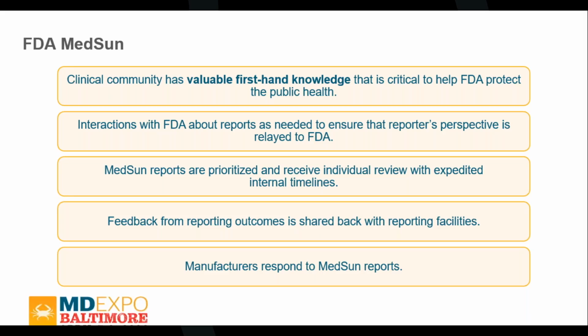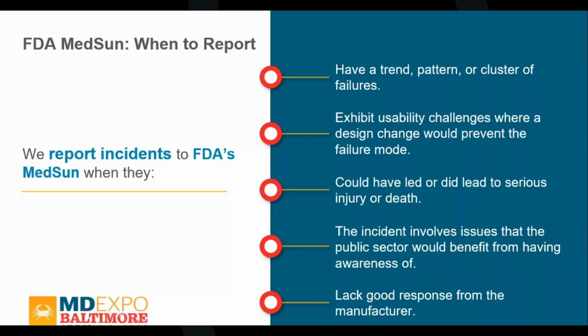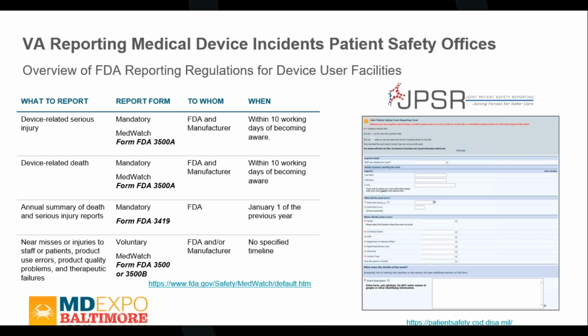And then, as we've talked about, the FDA and the manufacturers follow up a lot faster with a MedSun report. We get feedback from reporting outcomes, and that's shared with all of the MedSun user facilities. They publish a monthly report, and that can be quite valuable. And then manufacturers do respond to those MedSun reports. So when do we report incidents to MedSun? Well, we do this not for every incident, but we report incidents into MedSun when it has a trend, pattern, or cluster of failures, exhibits usability challenges where design change would prevent the failure mode. It could have led or did lead to serious injury or death. The incident involves an issue where the public sector would benefit from having knowledge of it, and or we're lacking a good response from the manufacturer, because these reports do get more heavy attention by the FDA and the manufacturers.